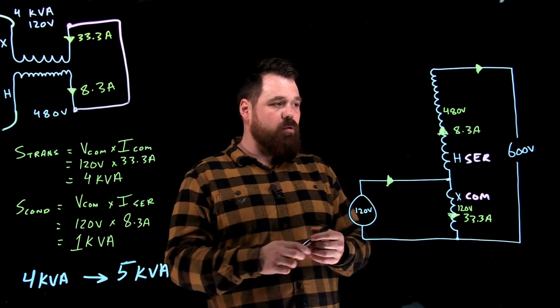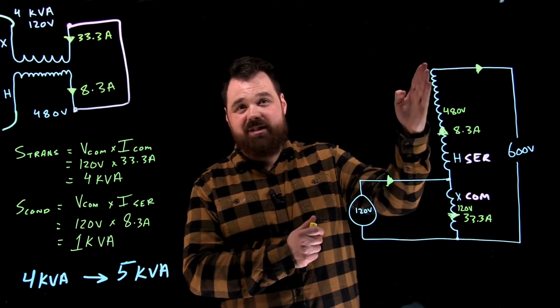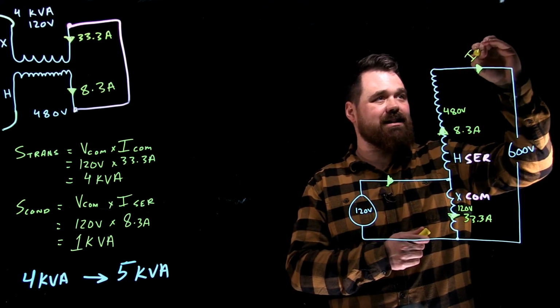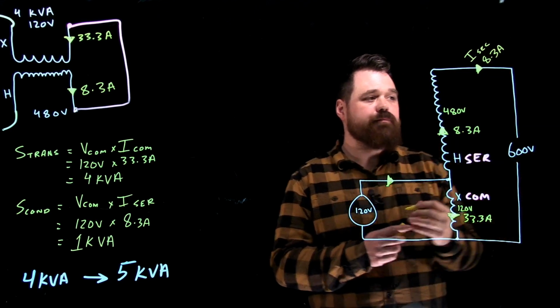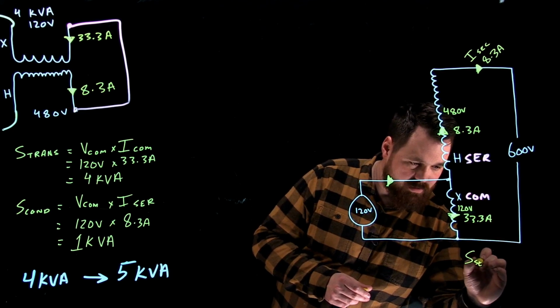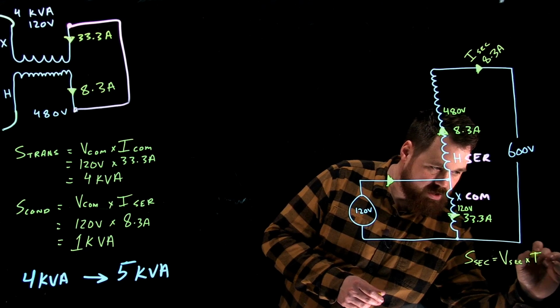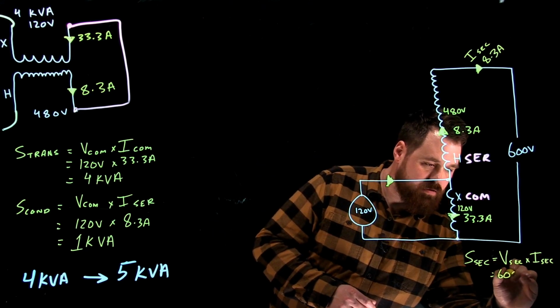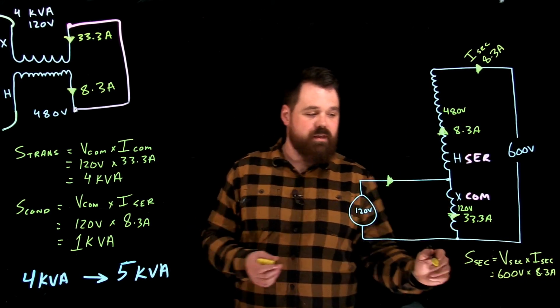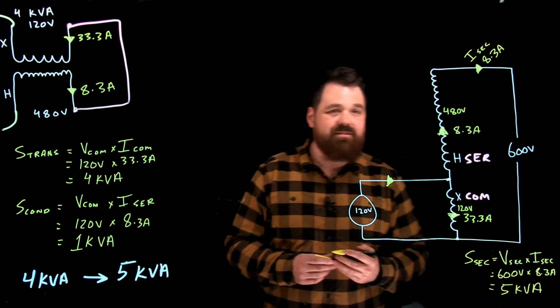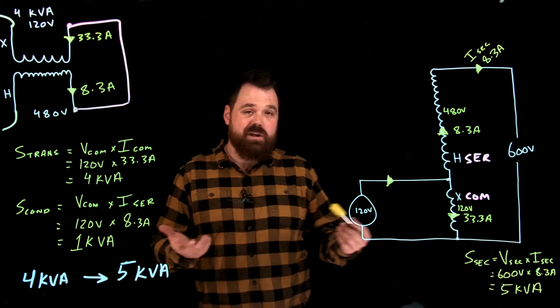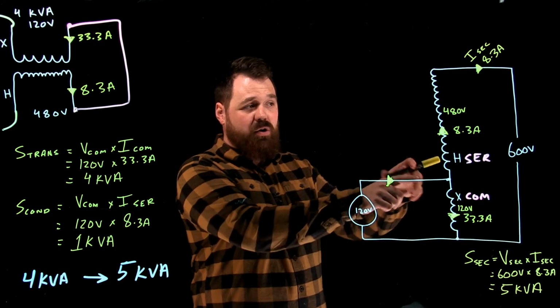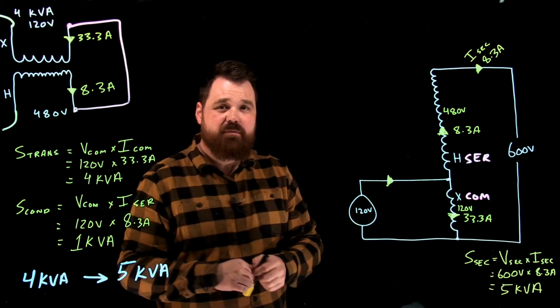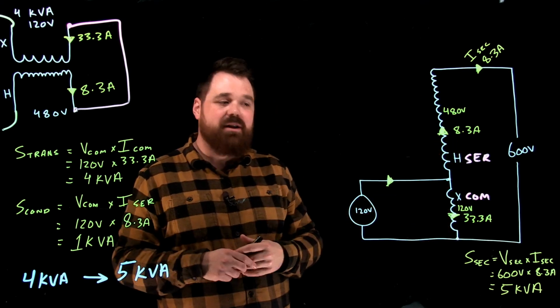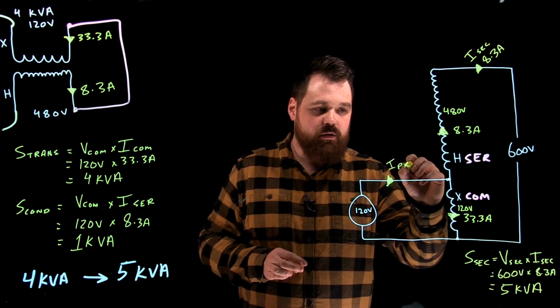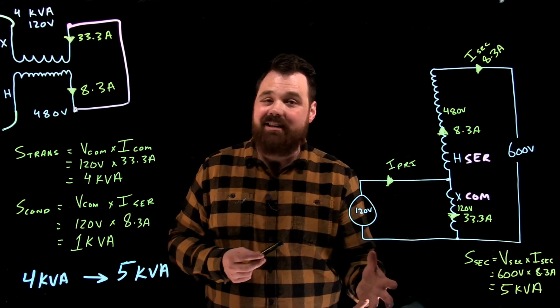And now we can prove that as well, right? If I take this series current of 8.3 amps flowing through my series winding, that's also going to be flowing here. We could also call that my secondary current, right? Well, S of my secondary would be voltage of my secondary times current of my secondary, well, 600 volts times 8.3 amps. That again just confirms that 5 kVA rating. So very, very cool. We could even go as far as to see it on the primary, right? Using Kirchhoff's current law, we know 8.3 amps flowed up, 33.3 amps flowed down. Well, 8.3 plus 33.3, I don't even have that number, but that would give me my I primary. And I could multiply my I primary times 120 to, again, get that 5,000 VA rating.